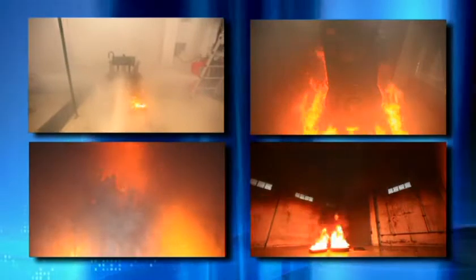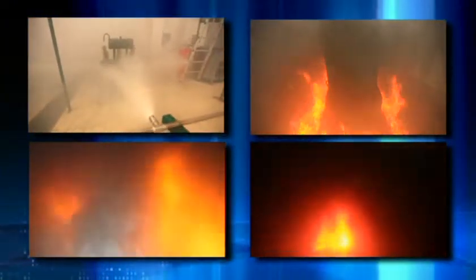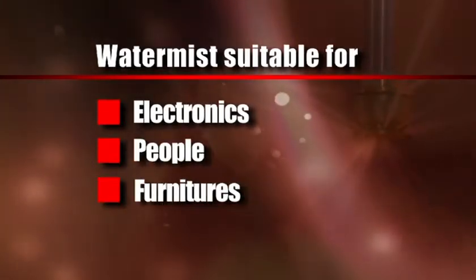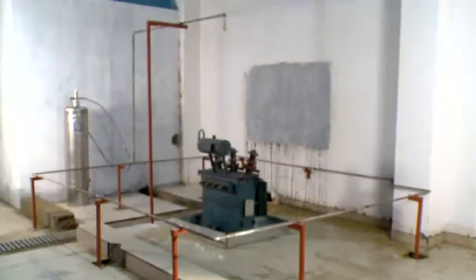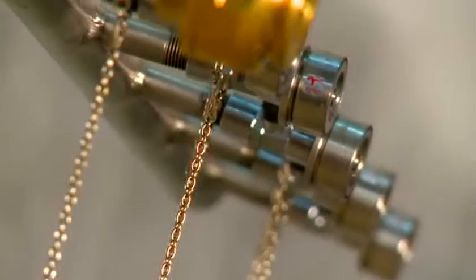A continuous stream of mist amounts to trillions of fire-extinguishing droplets attacking the fire. And the force with which they're thrown gives the droplets the power to break through heat currents and reach the fire source. When it reaches the fire, water mist envelops the flames, gets converted into steam, cuts off the oxygen supply, and reduces the temperature to below combustion levels. This threefold approach ensures that even the largest fire succumbs to water mist technology in minutes. Water mist keeps fire damage to a minimum and is suitable for a range of applications involving electronics, people, furniture, food production units, and more. Ceasefire offers a wide range of water mist products that fit all kinds of requirements, from portable fire extinguishers to complete systems. No matter the size of the application, water mist can take the fire on.